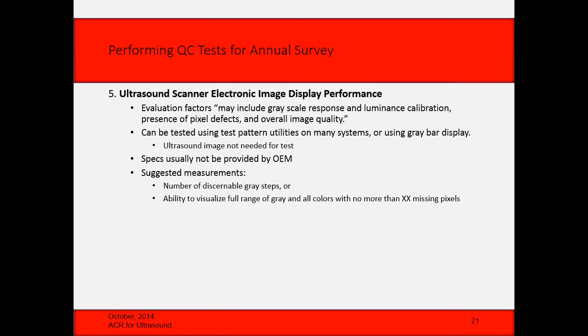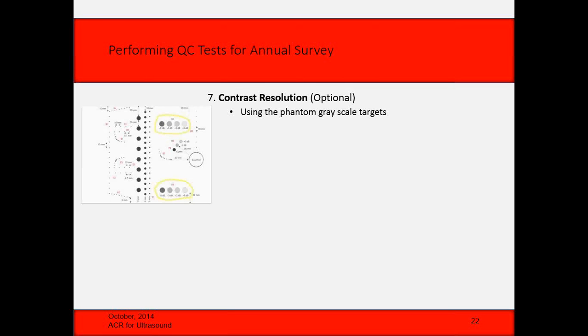Then you're also supposed to make sure that the display they're using to read the scans is working properly. So since so often these days that is not the ultrasound system itself, that's why they have this in here. So that would be the workstation, or if they're actually using printouts, the printouts. Contrast resolution is optional. Those other tests are required, by the way, for the annual survey. Contrast resolution is optional.